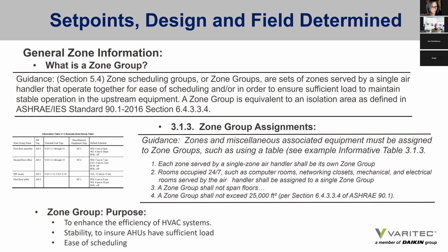There are zone group assignments. Zones and miscellaneous associated equipment must be assigned to the zone groups. Each zone served by a single air handler shall be its own zone group. Rooms occupied 24/7, such as computer rooms, networking closets, mechanical and electrical rooms, shall be their own assigned zone group. A zone group shall not span floors, and it shall not exceed 25,000 square feet. So the purpose of coming up with the concept of zone groups was to enhance the efficiency of the HVAC system, to provide stability and ensure AHUs have sufficient load to stay in operation, and for ease of scheduling as well.